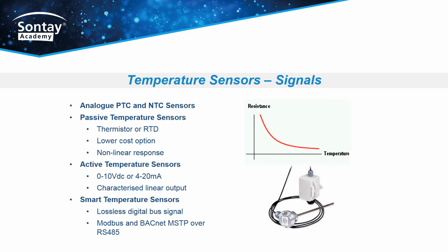Temperature sensors, signals. Controllers can receive data as signals from different types of sensors, such as analog PTC and NTC sensors, passive temperature sensors with thermistor or RTD. These are a lower cost option and have a non-linear response. There are active temperature sensors, which can be 0 to 10 volts DC or 4 to 20 milliamp. These are characterised by a linear output. Smart temperature sensors have lossless digital bus signal and Modbus and BACnet MSTP over RS485.